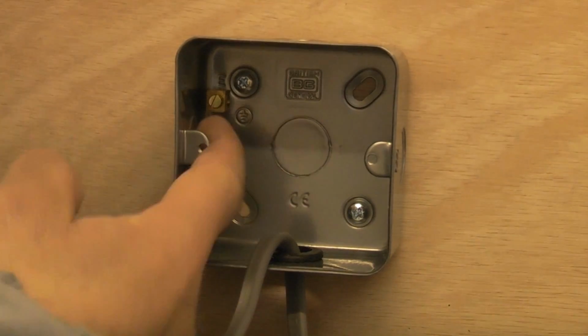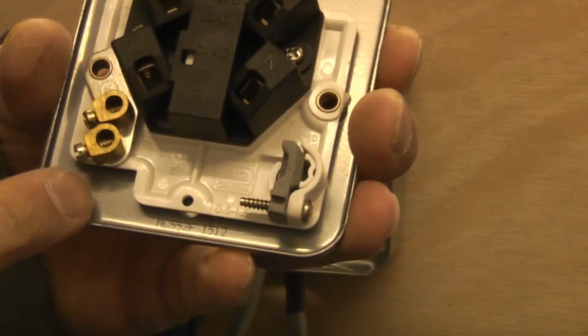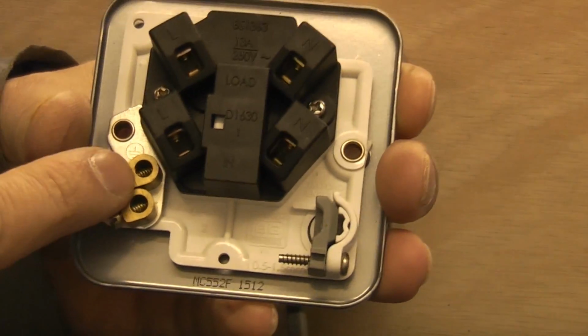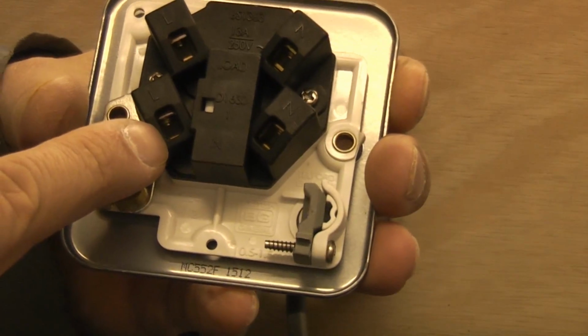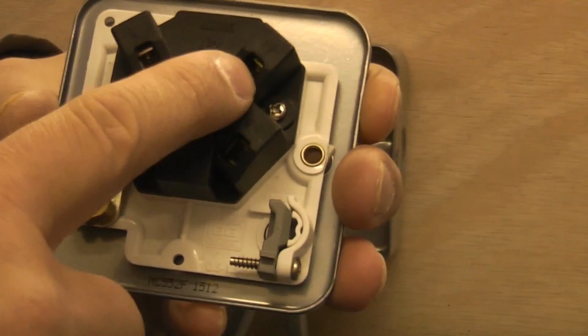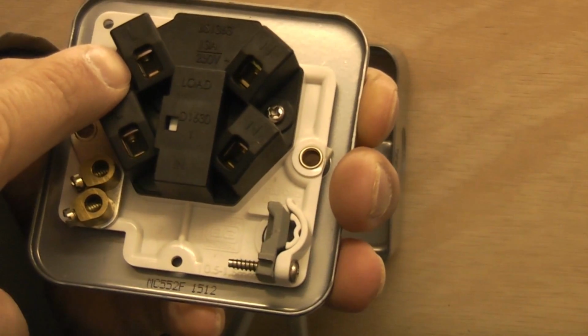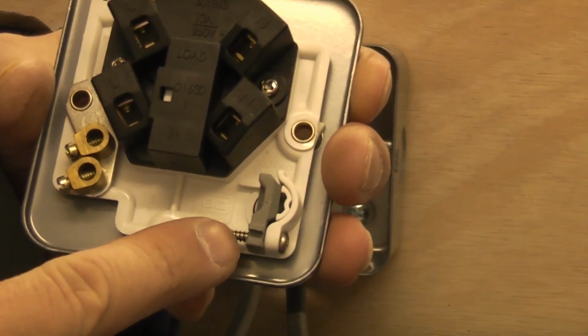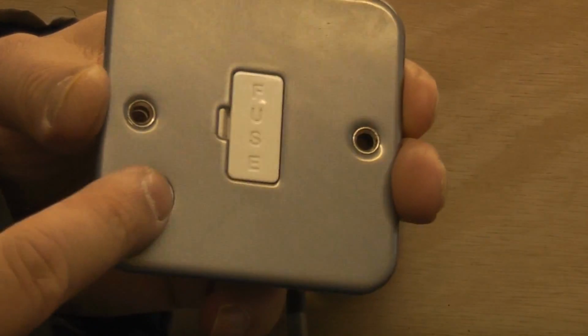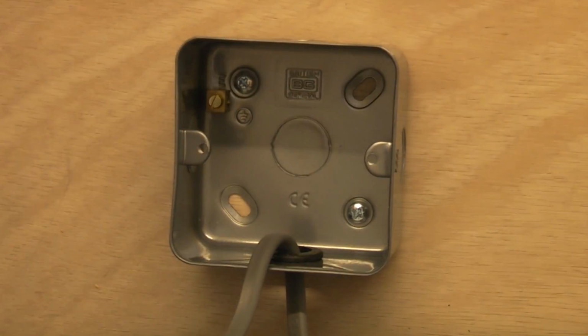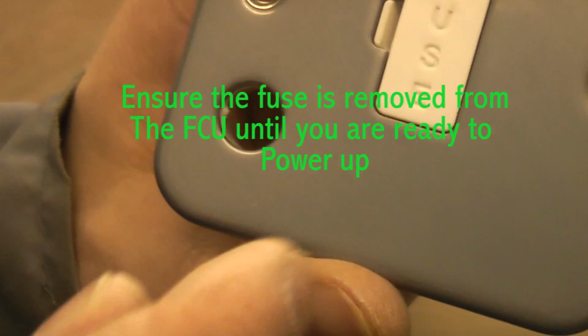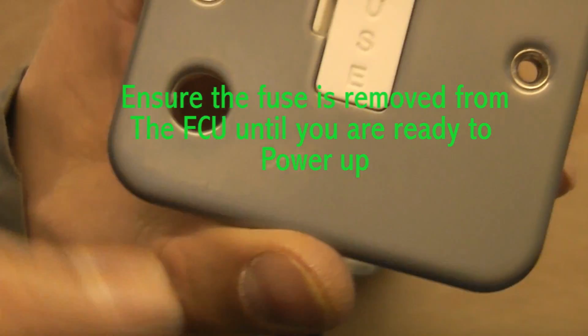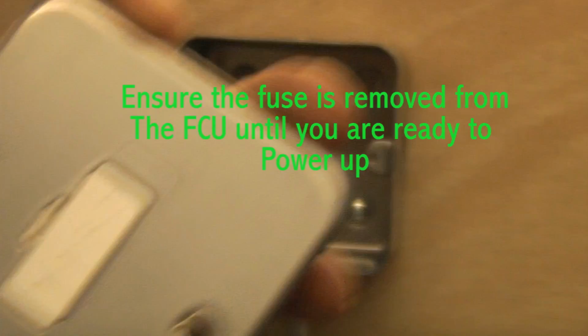If you look on the back there, you'll see that there's an earthing terminal, and then on the actual FCU itself we have 2 earthing terminals. We have a live in, neutral out and live out, and then at the bottom there we have a cord grip. So we're going to use that cord grip, which looks like that on that side, so we're going to remove that now. So I've now removed the blank that was in there. That will enable the cable to go through there.